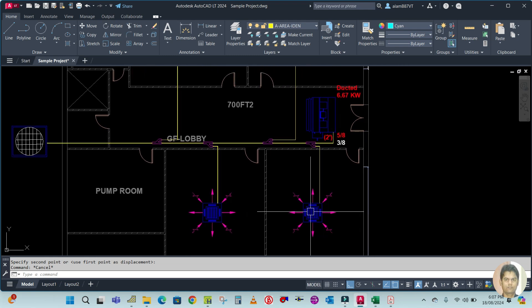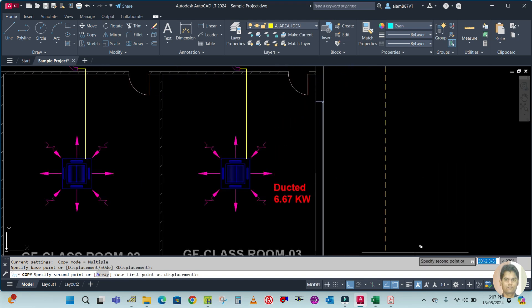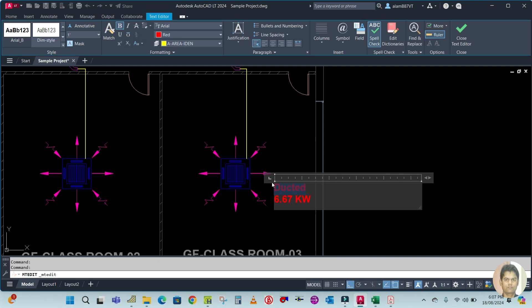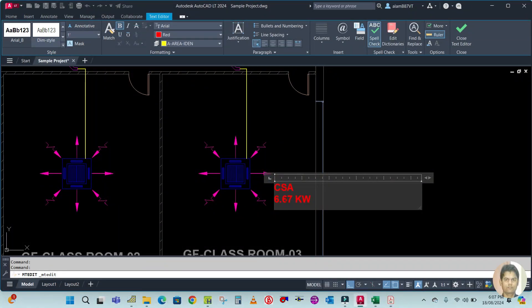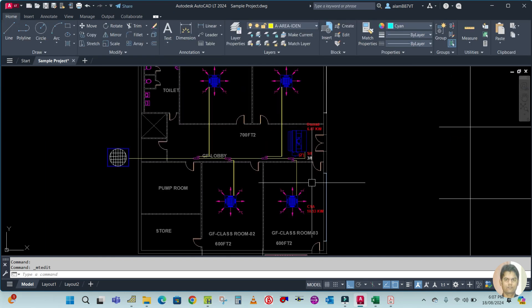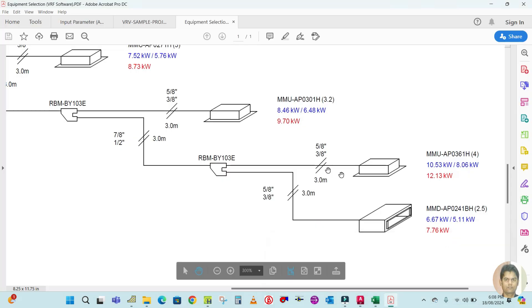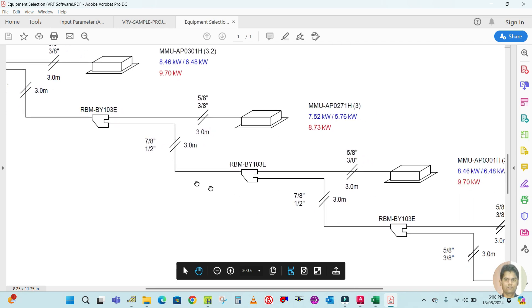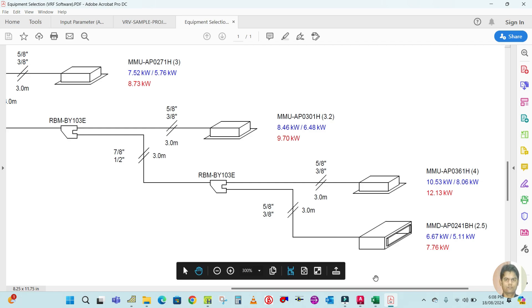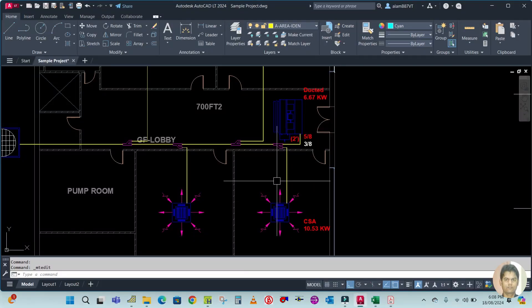Next is your cassette unit. Copy this text and place it here. You can check: CSA cassette type, cassette split. From the selection you can check 10.53 kilowatt. For the pipe size, also check here — 5/8 by 3/8. The length is given in the selection; enter the equal sign to select the unit and measure the actual length in the drawing.